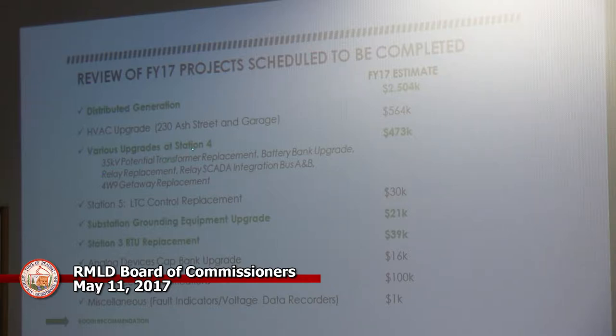Various projects at Station 4: we needed the 35 kV potential transformers, the battery bank is replaced now, the relays are all upgraded, and the relay and SCADA integration for bus A and B are all done.